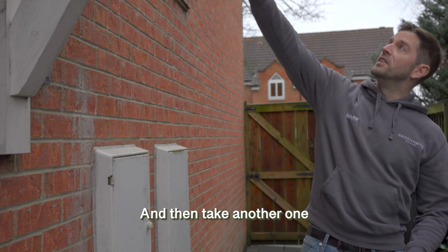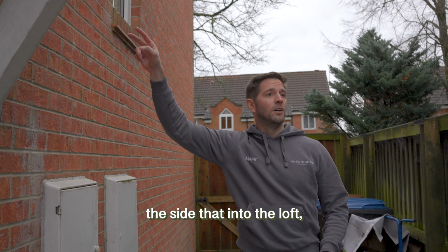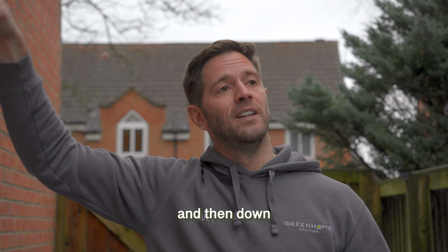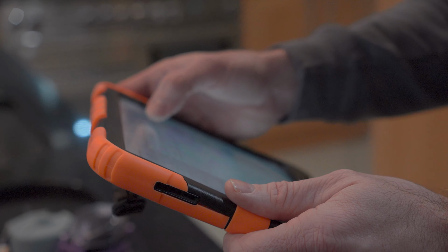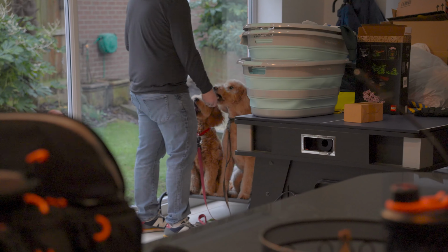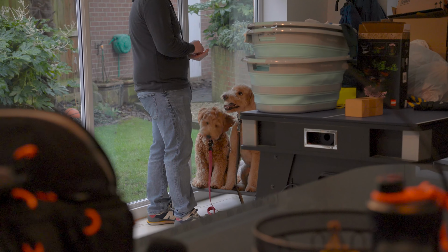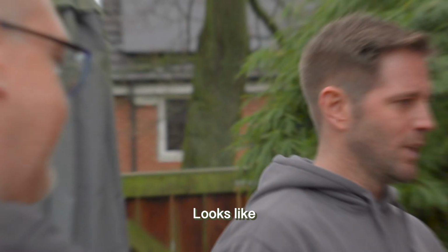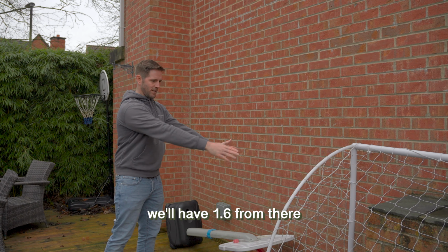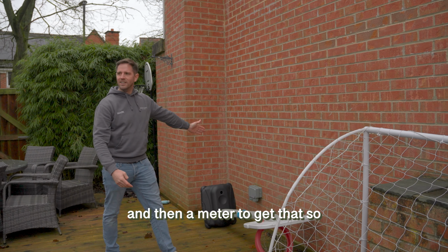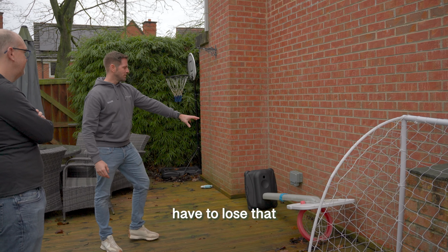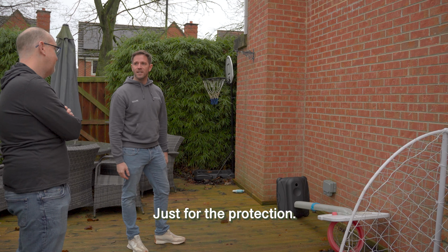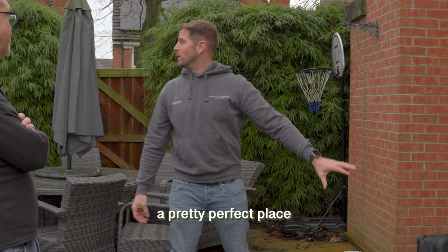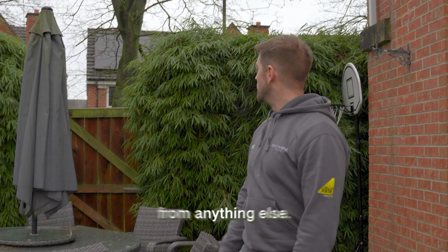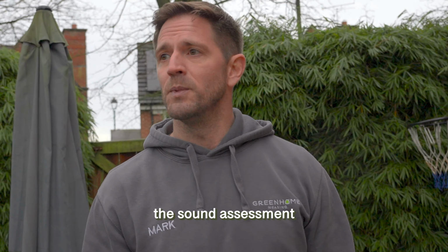Here, and then take another one straight up beside that into the loft, right the way across the loft, and then down for the heat pump. Like we'll have 1.6 from there, and then a metre to get that. So we're probably just going to have to lose that, just for the protection. That would be a pretty perfect place. It's well away from anything else, so it's going to pass the sound assessment no problem as well.